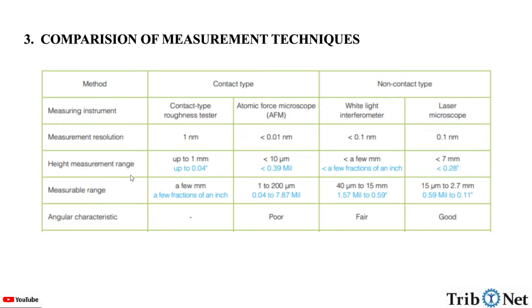Measurable range is a few millimeters for stylus measurement, 1 to 200 micrometers for AFM, 40 micrometers to 15 millimeters for optical interferometer, and 15 micrometers to 2.7 millimeters for laser microscope.